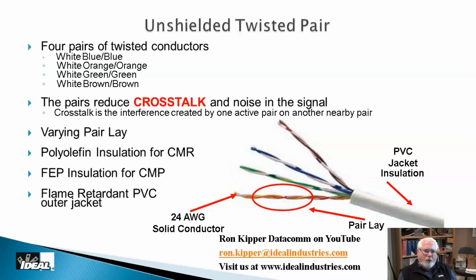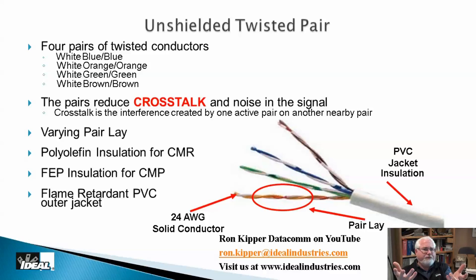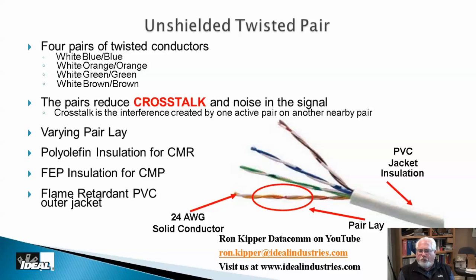The pairs reduce crosstalk and noise. Crosstalk is a signal generated on one conductor interfering with another — you can actually induce a signal into a conductor. Many of you have been on a phone line and faintly heard somebody else talking in the background. That's simply two telephone pairs sitting close together. A current down one conductor radiates a magnetic field, which induces a little voltage into the other pair. In data, that's a big deal and we need to eliminate it.